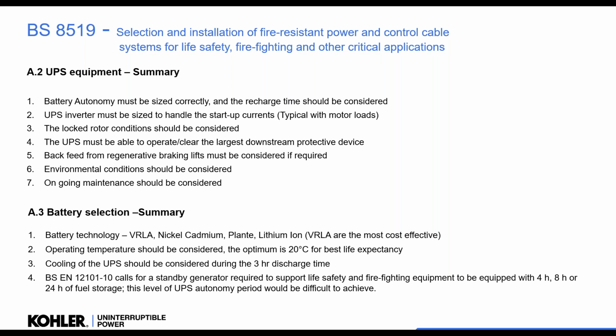It talks about the different battery technologies: VRLA, NICAD, Planté, lithium-ion, but recommends that VRLA is the most cost-effective, and we tend to agree with that. But we must operate it, as it says, at the optimum 20 degrees for the best life expectancy and performance. The UPS needs to be in the right environment and not overheat on a mains fail, because if it's a 3-hour discharge time, we want to make sure the environment is kept so the UPS doesn't trip on over temperature.